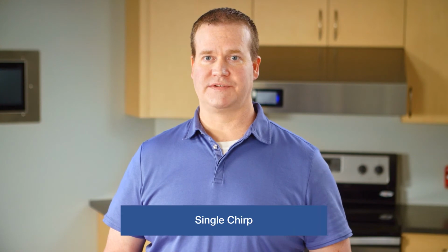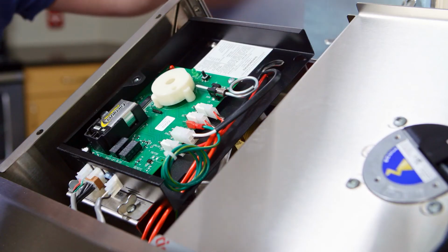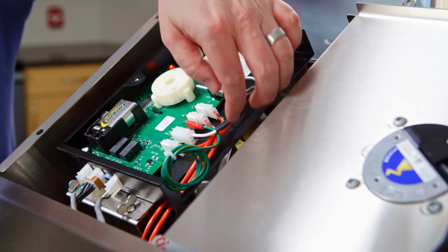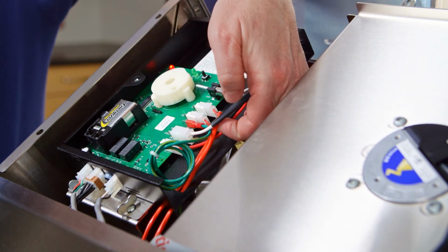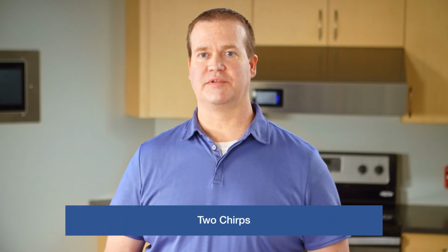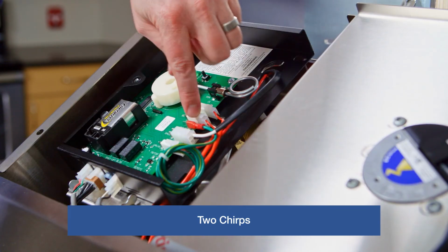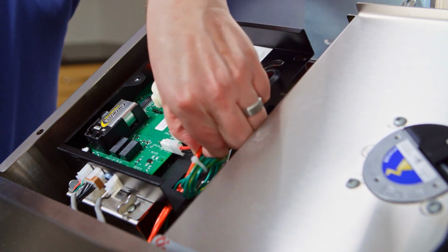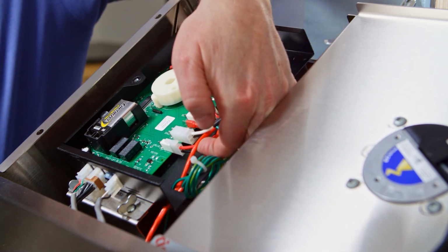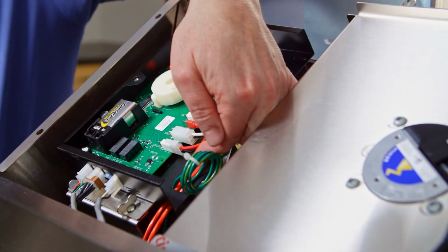As mentioned, the number of chirps during the fire suppression test indicates what may have gone wrong during the test. A single chirp from the buzzer indicates a potential problem on the Fire Sensor 1 circuit or the remote pull station has an issue. Check the connections for Sensor 1 at the circuit board. If connections and wiring test OK, replace the sensor. 2 chirps from the buzzer indicates a potential problem on the fire sensor 2 circuit. Check the connections for sensor 2 at the circuit board. If connections and wiring test OK, replace the sensor.